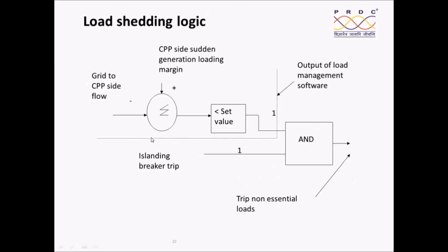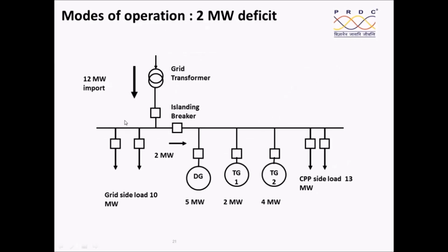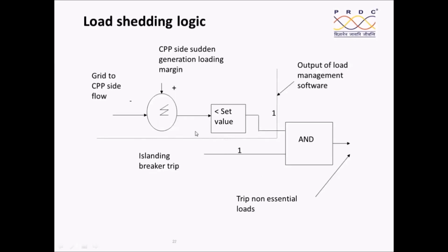Therefore, the logic for this can be: grid to CPP side flow, take the negative of that, and CPP side sudden generation load margin, how much margin is available. For example, load margin is 0 here. I don't have any margin. Grid to CPP side flow is 2 megawatt now. Therefore, it is minus 2 megawatt that comes here. Set value is 0, for example. Therefore, it is less than the set value. Therefore, this logic becomes 1. Islanding breaker trip is 1. Therefore, trip non-essential loads.